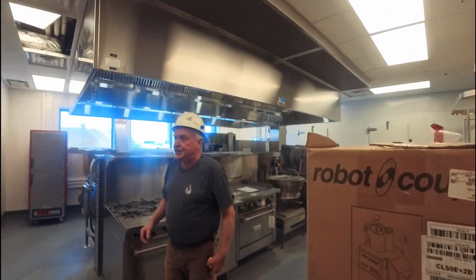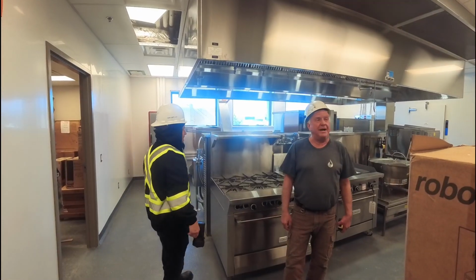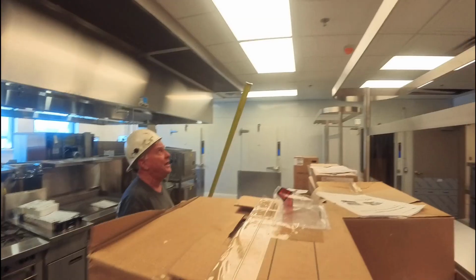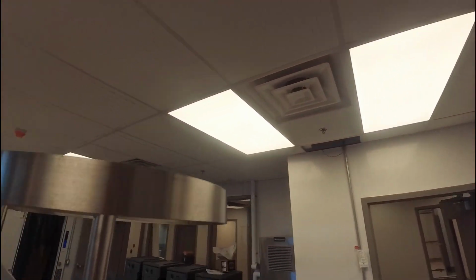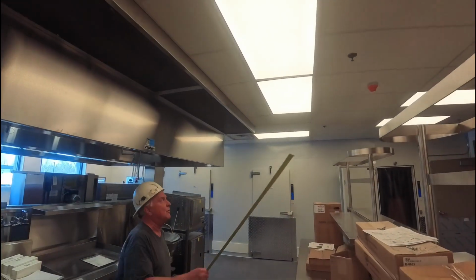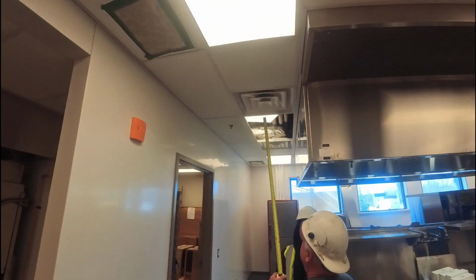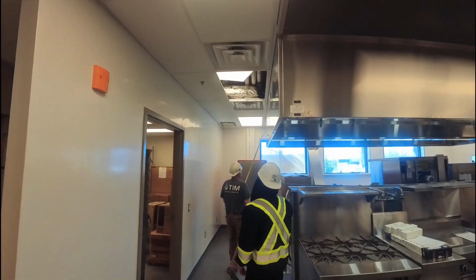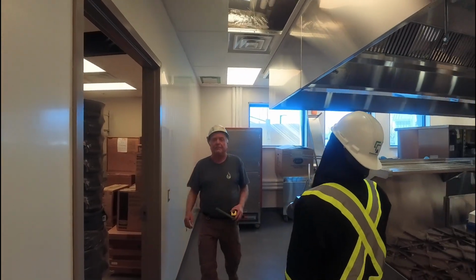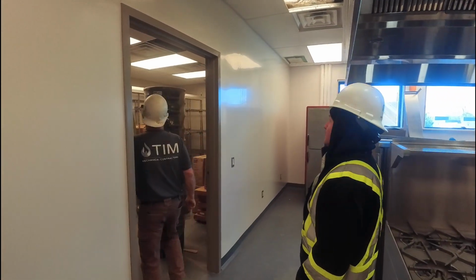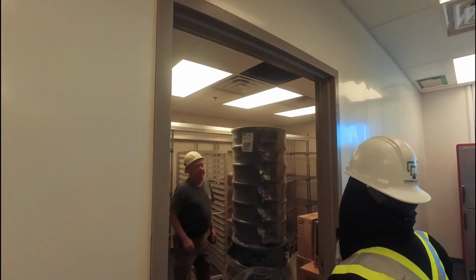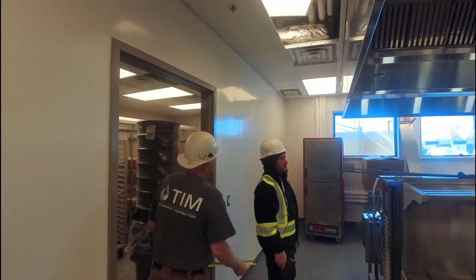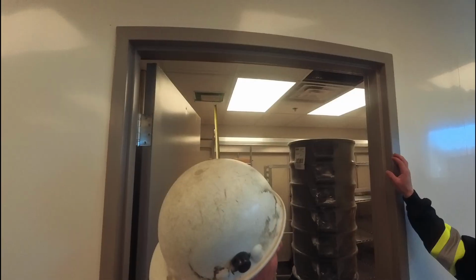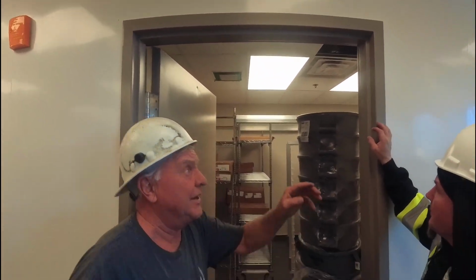The kitchen is operated by its own HVAC device. It's HVAC number 1, sitting on the roof right above us. What it's feeding, HVAC number 1, is each one of these supply diffusers, 24 by 24 supply diffusers for air coming into the room itself, all the way around. I believe there's 9 in total. It also feeds the diffuser that's in the dishwasher room, and this kitchen storage room has 2 of them as well. When you have a supply diffuser, you have to have a return diffuser, so it's coming off of HVAC number 1 as well. Each room, there's a 12 by 12 in this guy. I think that's a 14 by 10 over there. And it also has a return in the corner there, and one above my head, if I recall. Yeah, for the kitchen area itself.